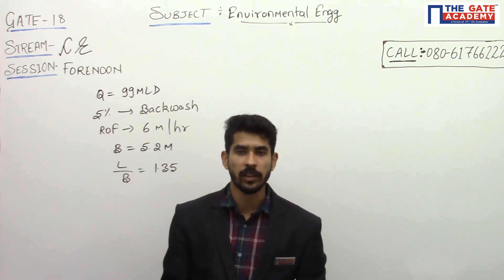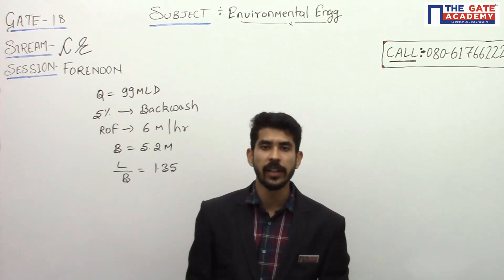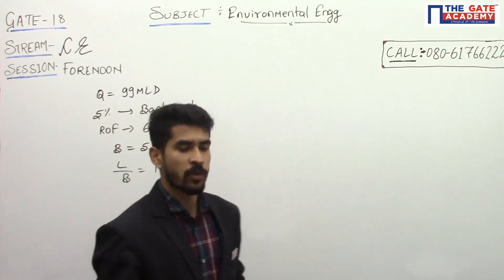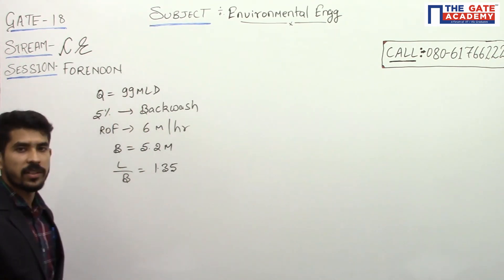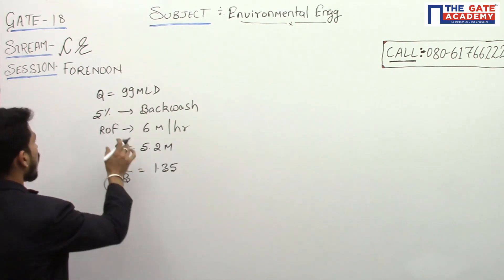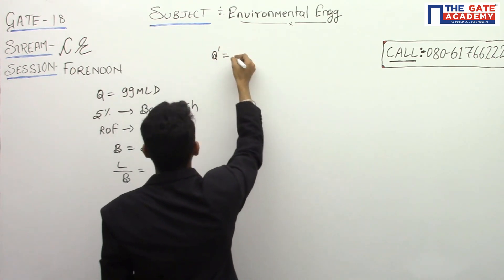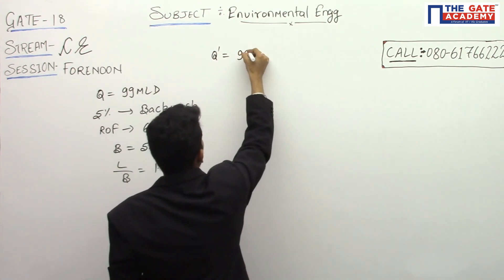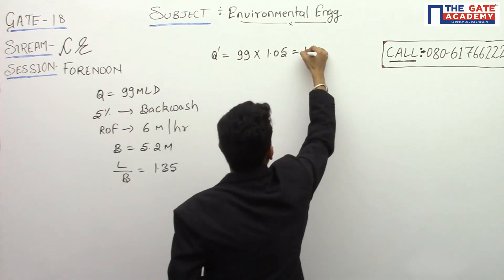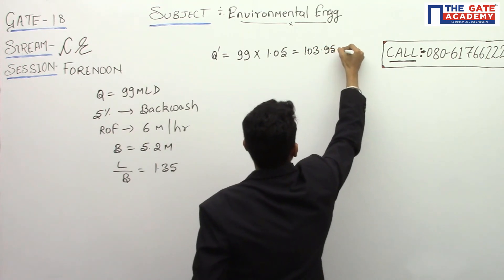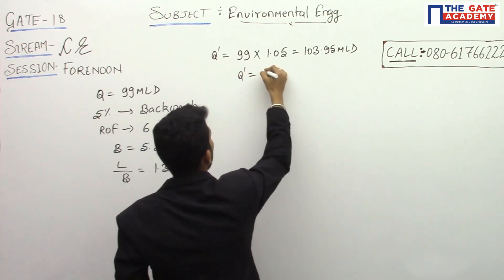The options are: Option A is 19, Option B is 20, Option C is 21, and Option D is 22. Now, 99 MLD is the treated water, out of which 5% is the backwash water. So an additional 5% is required for backwashing, making our effective discharge 99 MLD plus 5%, which equals 103.95 MLD.